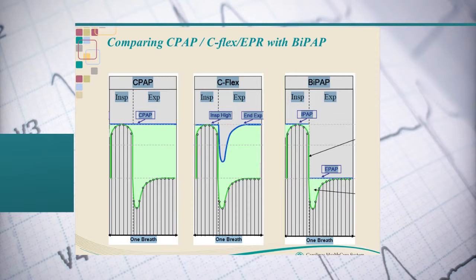The way the air is delivered now is also getting more sophisticated. It used to be that CPAP would just blow a fixed amount of air, and whether the patient was inhaling or exhaling, the same amount of air pressure was going both ways. Well, now there are newer ways of pushing the air forward. One of them is where the air pressure relaxes. We call that expiratory pressure release, or some device manufacturers call that C-flex, where as the patient exhales, the pressure drops, and then it gradually increases again.